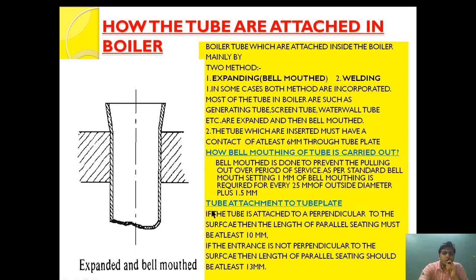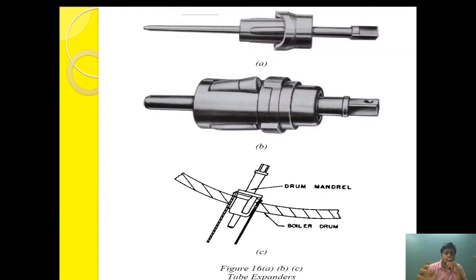For tube attachment to a tube plate: if the tube is attached perpendicular to the surface, the length of the parallel seating must be at least 10 mm. If the entrance is not perpendicular to the surface, then the tube attachment should be at least 13 mm. These are the things we need to keep in mind while expanding the tube.